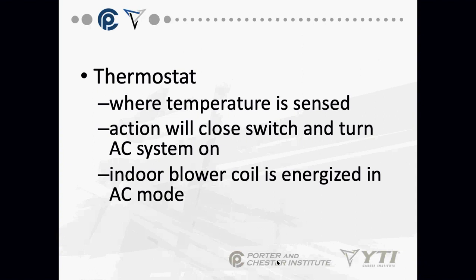The thermostat is where the temperature is sensed. The action will close a switch and turn the AC system on. The indoor blower coil, and we're going to talk about that on our schematics, is energized in AC mode. Okay, so we have two things that energize when we talk about air conditioning. We energize the outside unit, and we energize the indoor blower to move the air around the house. Okay, those two things have to come on for our air conditioning to work. Those are all controlled in air conditioning from the thermostat. Okay, the blower and the outdoor unit is controlled from the thermostat.